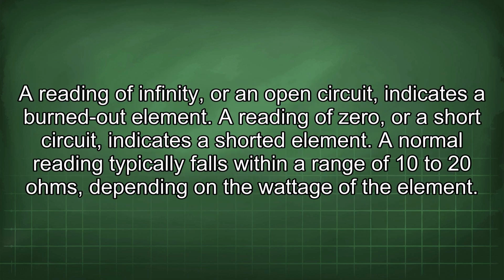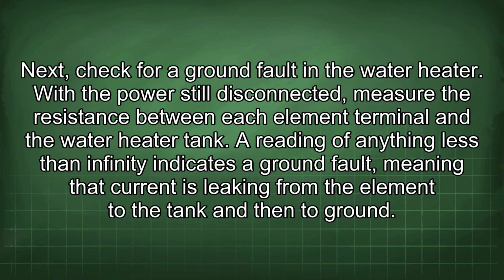A reading of infinity, or an open circuit, indicates a burned out element. A reading of 0, or a short circuit, indicates a shorted element. A normal reading typically falls within a range of 10 to 20 ohms, depending on the wattage of the element. Next, check for a ground fault in the water heater. With the power still disconnected, measure the resistance between each element terminal and the water heater tank.